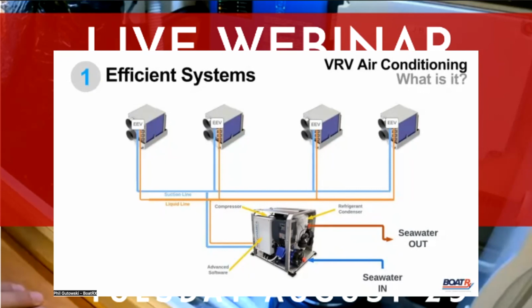And that liquid refrigerant then travels out the orange liquid line where it's distributed to each of these air handlers. And when it gets to the air handler, it reaches what's called an electronic expansion valve, an EEV, which regulates the flow of that high pressure liquid refrigerant into the copper evaporator coil. And that EEV is responding to software that's telling it just how much to open and how much refrigerant to feed into the coil. Therefore, maintaining the temperature of the coil at usually a temperature just above freezing. So it doesn't freeze, but it maximizes the dehumidification effect.